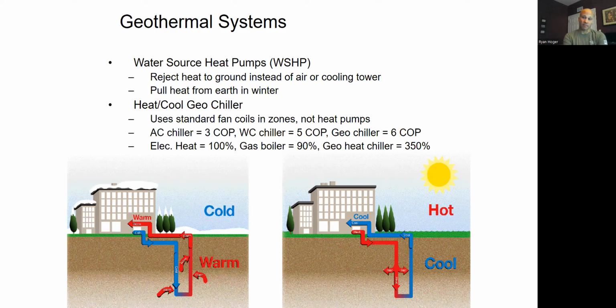And then in the wintertime, that water would be, we still call it the condenser water actually, but it'd be my warm water. It would be my evaporator water, but no one says that. And I am then afforded the ability to have a pretty efficient system. Geothermal is one of the most efficient things you can do. Water-cooled chillers are really efficient. And when I combine those two things together, I can get some really sick efficiencies, which is phenomenal.